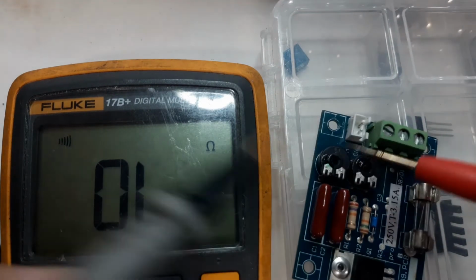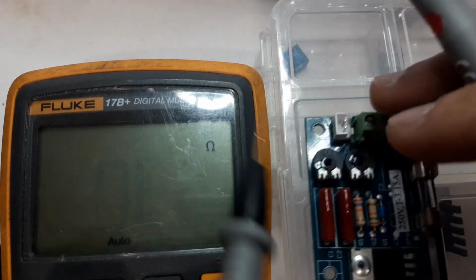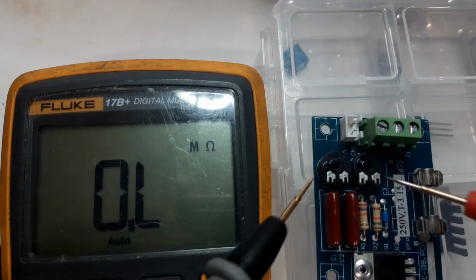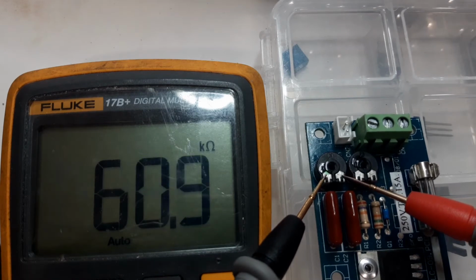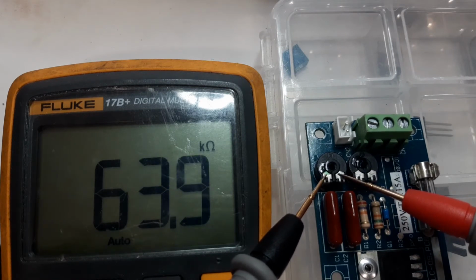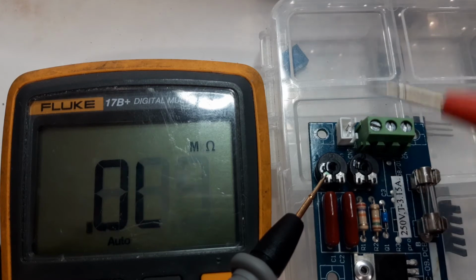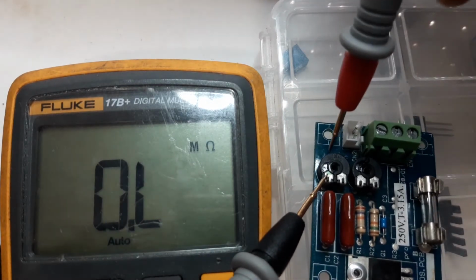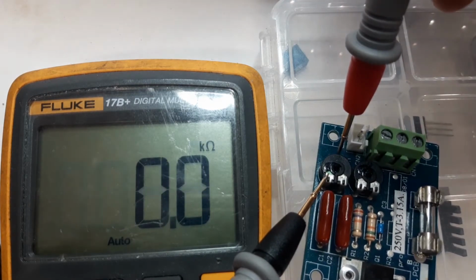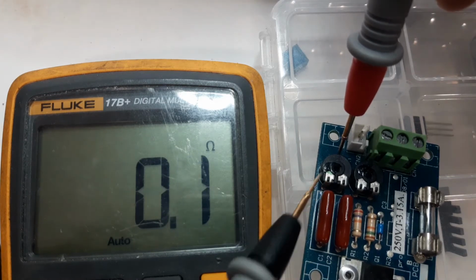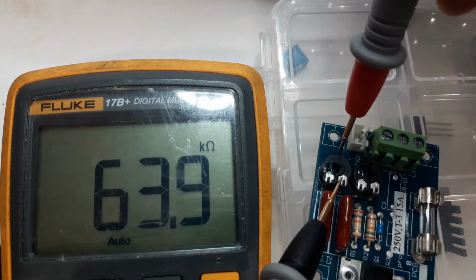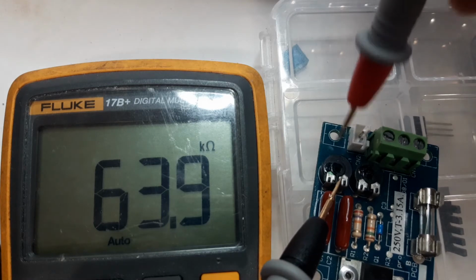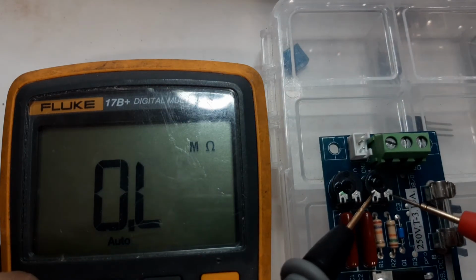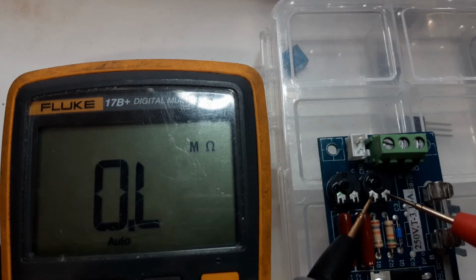So the next thing is, let's check this one. Okay, meter in resistance mode. Let us check this. We got 63.9K. At this point, we have 0.1 ohms. We have 63.9K. How about this one? It's reading OL.